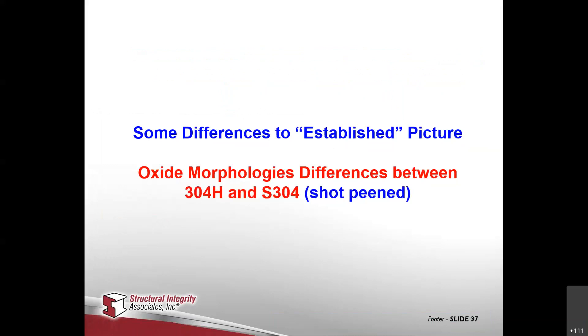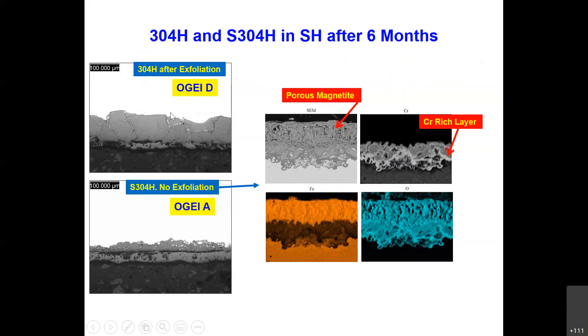One important difference for austenitic alloys is the behavior of shot-peened alloys. Under the same time and magnification, standard 304 or 300 series alloys have the outer magnetite layer completely exfoliated leaving only iron-chrome spinel, whereas the shot-peened Super 304 alloys have both oxide layers still in place. It is very rare for these shot-peened alloys to exfoliate, because the chromium map shows a chromium-rich layer all along the surface of the alloy, which slows down the rate and prevents exfoliation.